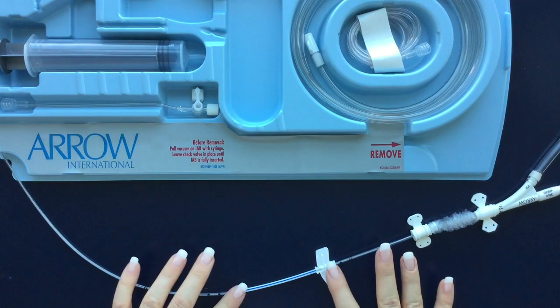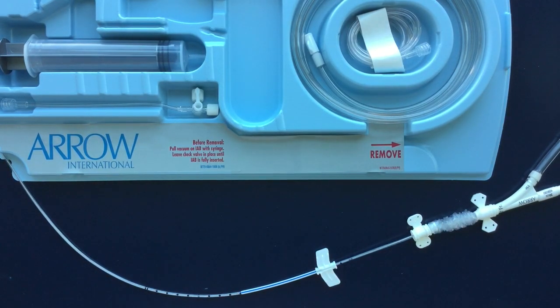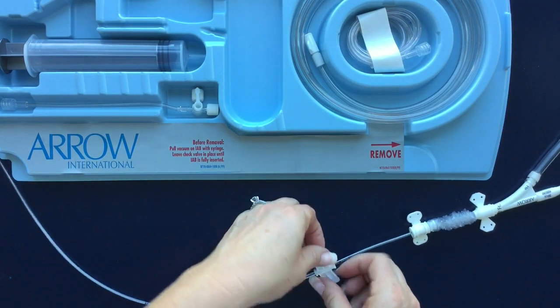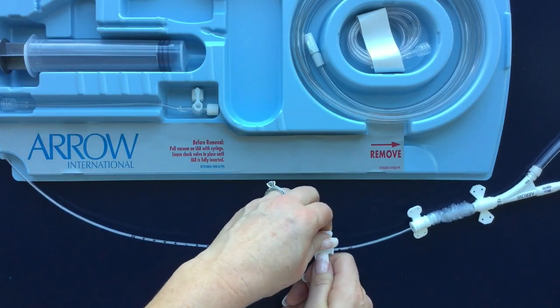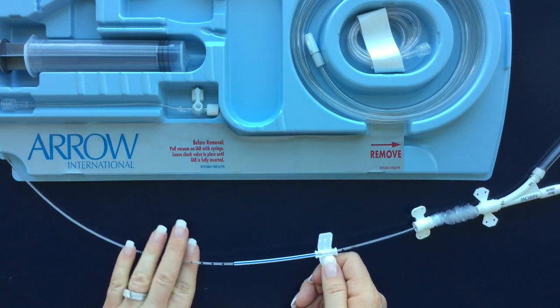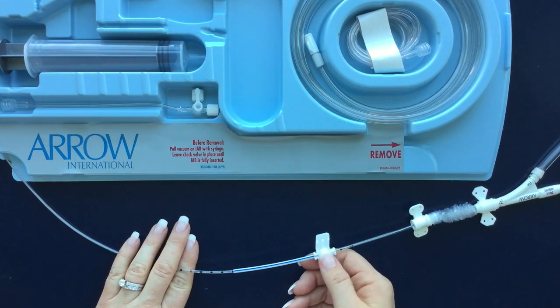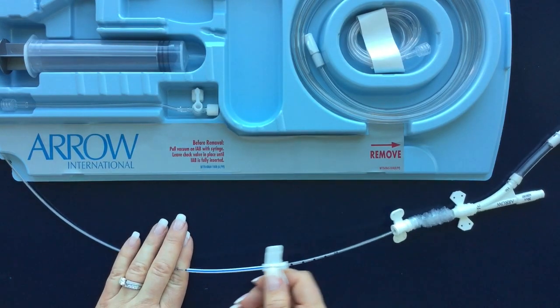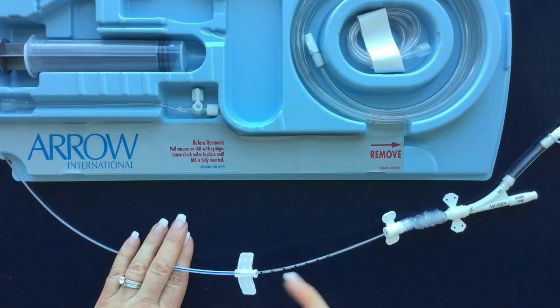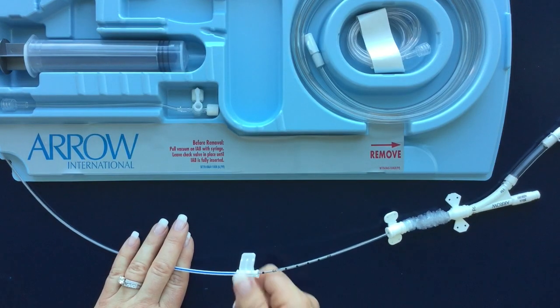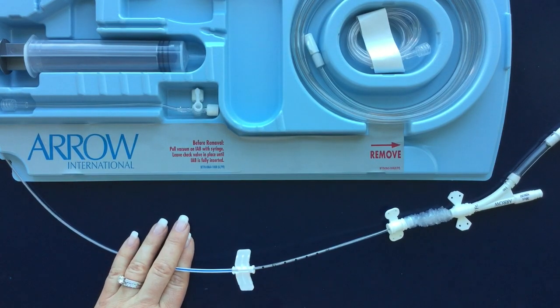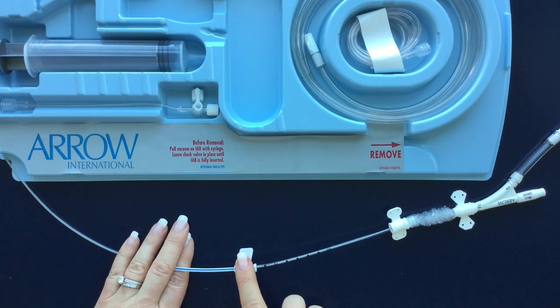The hemostasis device is to be used only with sheathless insertions. If you are inserting the balloon catheter through a sheath, this needs to be removed and you simply crack up, crack down, and peel it away. If you have chosen to go sheathless, you can advance this hemostasis device into the puncture site until you get a drop of blood and then go 1 centimeter more. That will help tamponade the ooze through the skin tract to the insertion site.